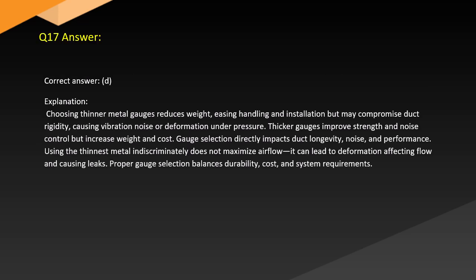Answer. Correct answer, D. Explanation. Choosing thinner metal gauges reduces weight, easing handling and installation, but may compromise duct rigidity, causing vibration noise or deformation under pressure. Thicker gauges improve strength and noise control, but increase weight and cost. Gauge selection directly impacts duct longevity, noise, and performance.